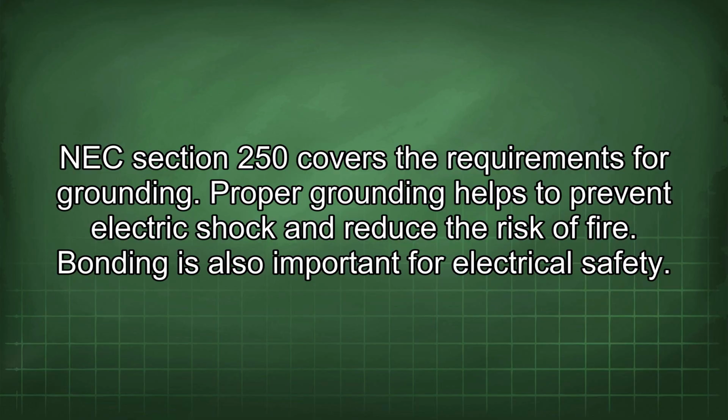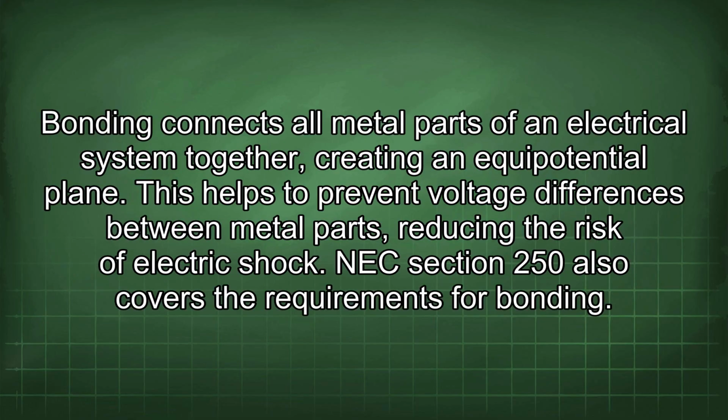Bonding is also important for electrical safety. Bonding connects all metal parts of an electrical system together, creating an equipotential plane. This helps to prevent voltage differences between metal parts, reducing the risk of electric shock. NEC Section 250 also covers the requirements for bonding.